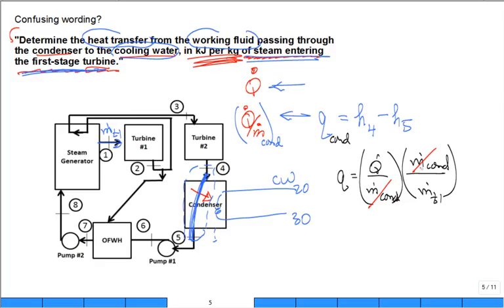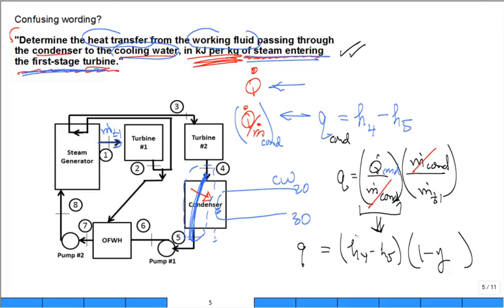Won't it be q dot in the condenser per mass flow rate entering the first turbine stage? Then I say, oh, if I just focus on the heat exchanger, I already know what that is — that's H4 minus H5. And then what is this term? 1 minus y. So there you go. Does that make sense? That's what I'd be asked to solve for: calculate the enthalpies at 4 and 5, get the difference, calculate the mass fraction y diverted to the open feed water heater, and then make the calculation.